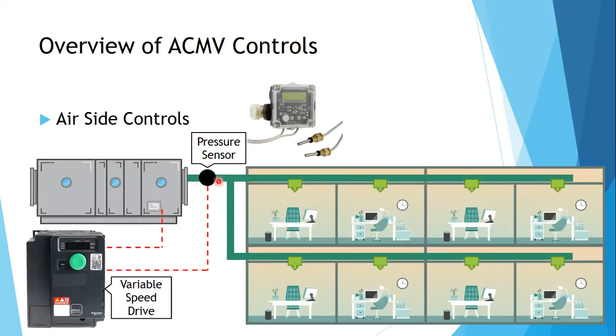Okay. So this pressure sensor is monitoring the pressure on the main duct. This pressure sensor kind of looks like this. It ensures that at this point there's a constant pressure. This pressure will be able to maintain the pressure across all the ducting system. So even though this guy over here closed his aircon unit, all these other guys will still have enough air. So how will this unit know if it's going up or going down?